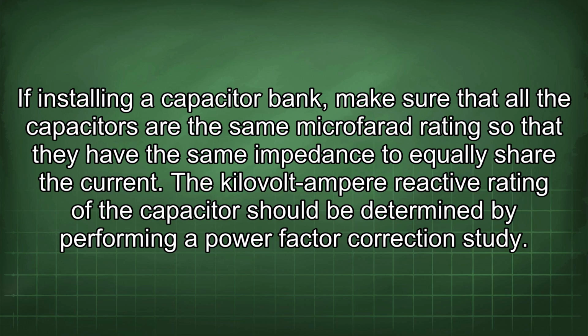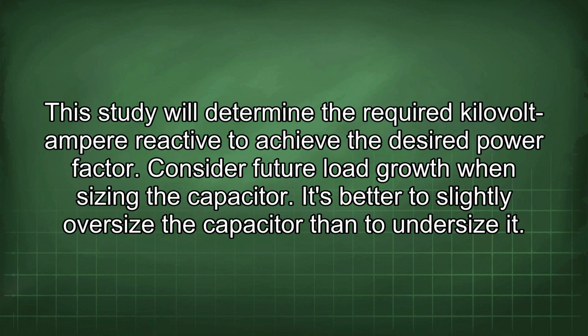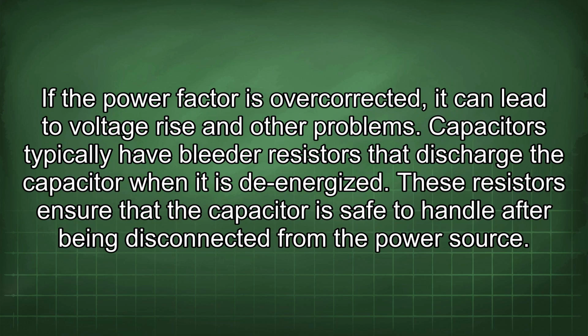The kilovolt ampere reactive rating of the capacitor should be determined by performing a power factor correction study. This study will determine the required kilovolt ampere reactive to achieve the desired power factor. Consider future load growth when sizing the capacitor. It's better to slightly oversize the capacitor than to undersize it. If the power factor is overcorrected, it can lead to voltage rise and other problems.